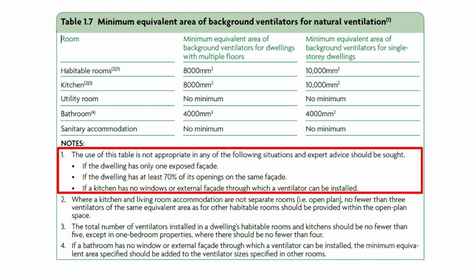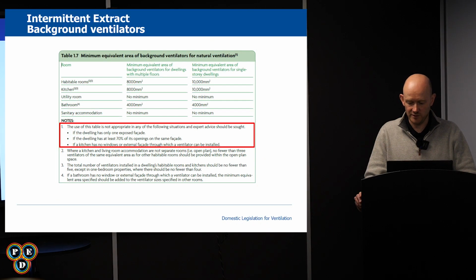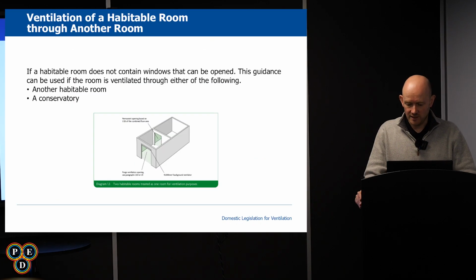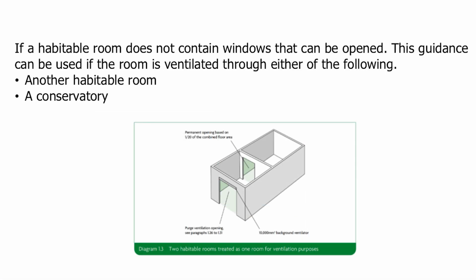A key note to be aware of is that background ventilators are not recommended in dwellings with only one exposed facade, or if a dwelling has at least 70% of its openings on the same facade. This will mean that apartments will likely need to move towards mechanical extract ventilation or mechanical ventilation with heat recovery. If there is a habitable room that does not have any windows, you will need to ventilate through another room. In order to comply with this, there should be a permanent opening between the two rooms of at least 1/20th of the combined floor area of the two rooms. Background ventilators of at least 10,000 millimetres squared equivalent area and purge ventilation should be present.